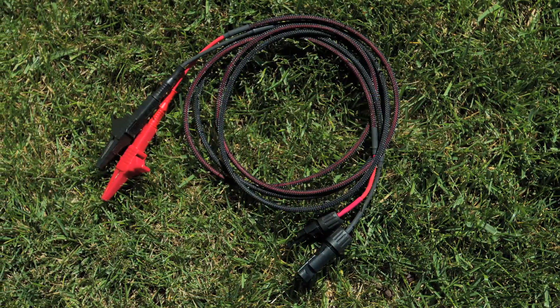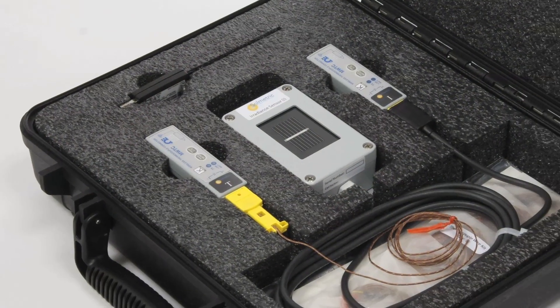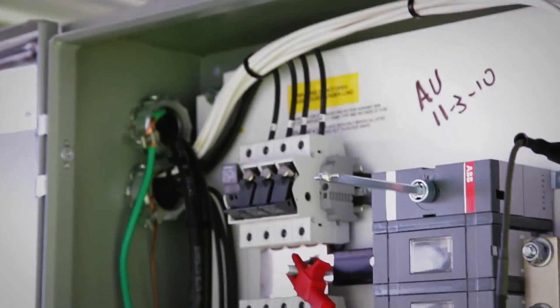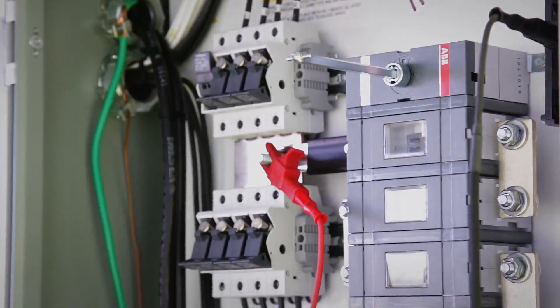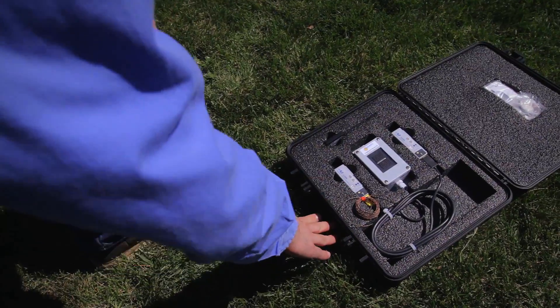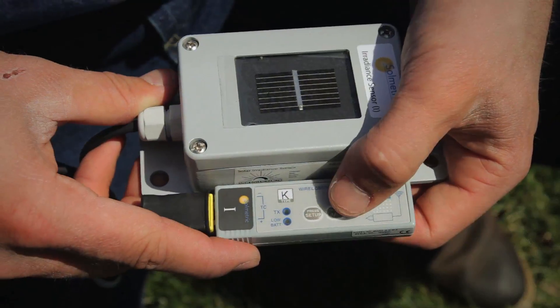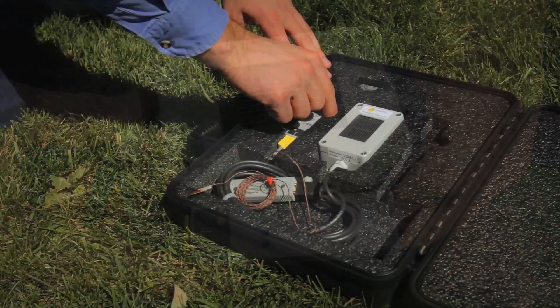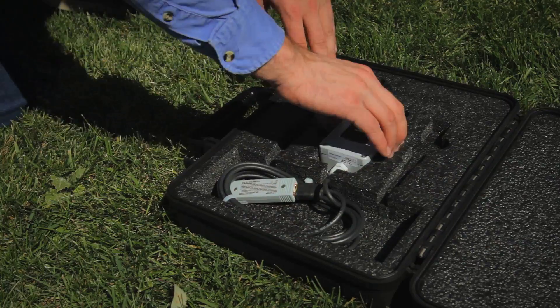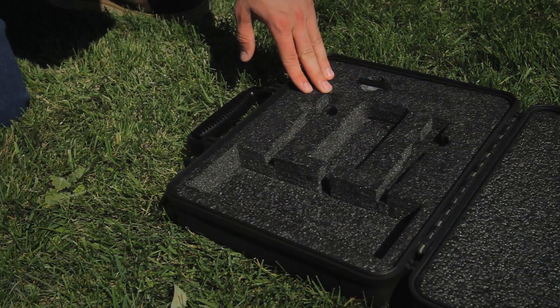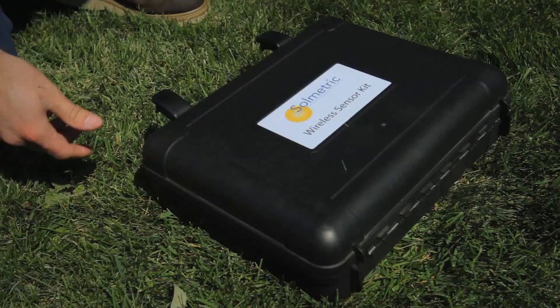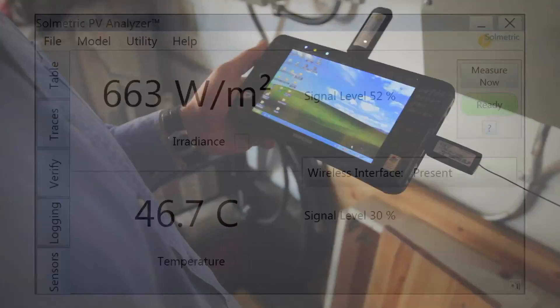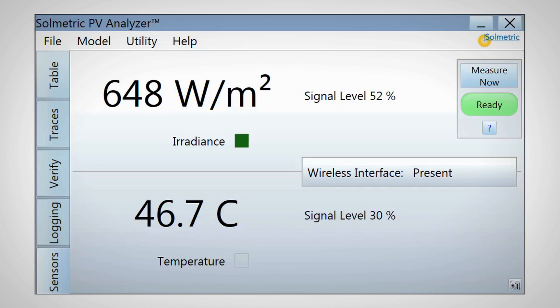Other optional accessories include PVA test leads and the wireless PVA sensor kit. The PVA test leads are five feet long and terminate in high current alligator clips. Irradiance and temperature are normally measured to ensure accurate model calculations. These values are constantly changing, and irradiance in particular can change very rapidly. The wireless PVA sensor kit includes an irradiance sensor and a thermocouple temperature sensor to provide nearly simultaneous irradiance and temperature inputs to the performance model. Both sensors interface wirelessly with the PC, and readings are continuously updated in sync with the IV curve measurements.